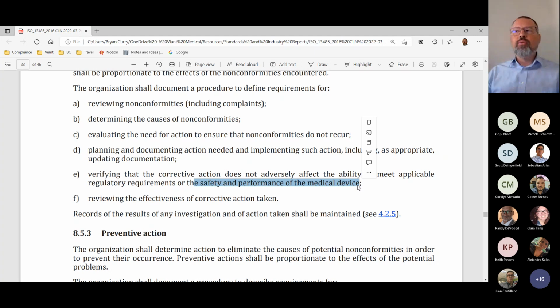Remember, conceptually, risk management is a balancing act. No medical device is without its potential to have failure modes occur. But part of your risk management process, as early as the design stages, is to demonstrate that the overarching benefits of having this medical device in the field outweigh the potential of these failure modes. And so that would be another way that you would use that type of justification to say, our solution is not a perfect solution, but the benefits far outweigh the downsides.